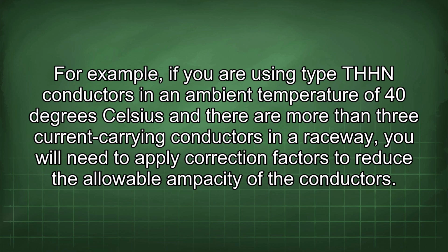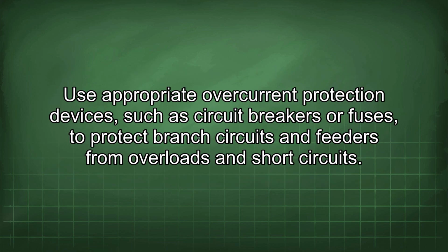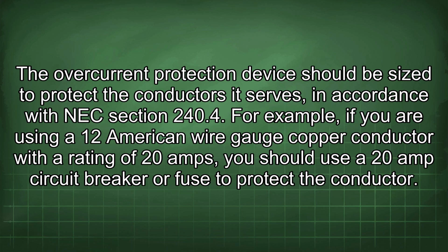of the conductors. Use appropriate overcurrent protection devices, such as circuit breakers or fuses, to protect branch circuits and feeders from overloads and short circuits. The overcurrent protection device should be sized to protect the conductors it serves, in accordance with NEC Section 240.4. For example, if you are using a 12 American wire gauge copper conductor with a rating of 20 amps, you should use a 20 amp circuit breaker or fuse to protect the conductor.